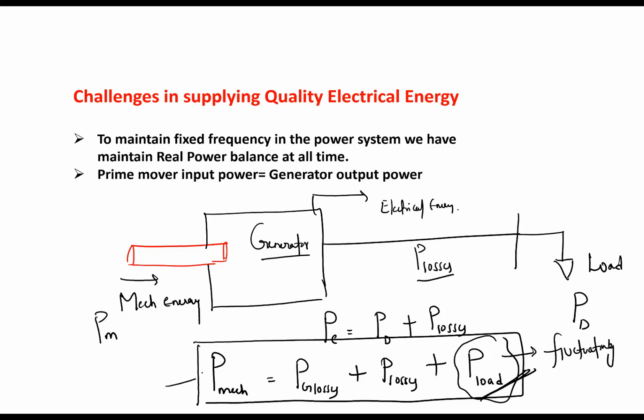To meet this continuously fluctuating load, we have to adjust the mechanical input given to the generator, the prime mover input. So the complete frequency control depends upon matching this equation. If you achieve exact matching, exact equilibrium, the frequency is constant at 50 Hz in India. This equation is called the real power balance: you have to match the prime mover input with the total generator losses plus transmission losses plus the real power demanded by the load.